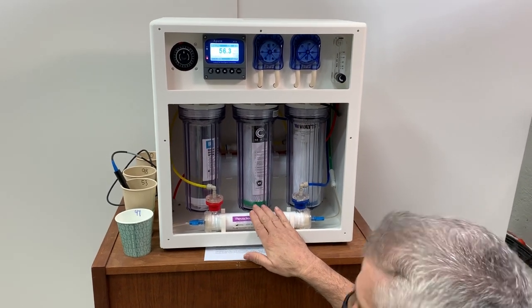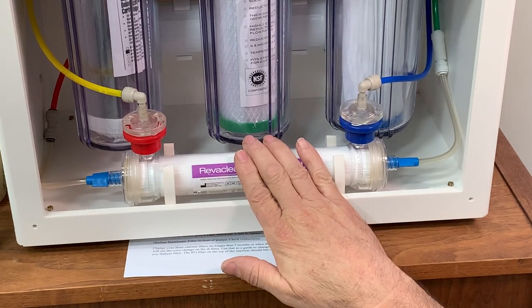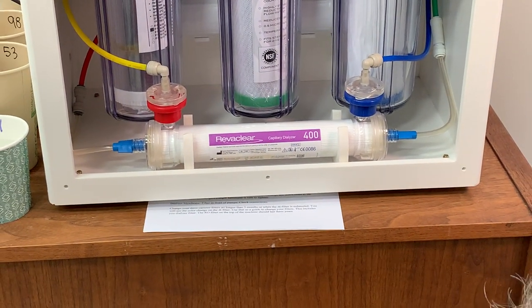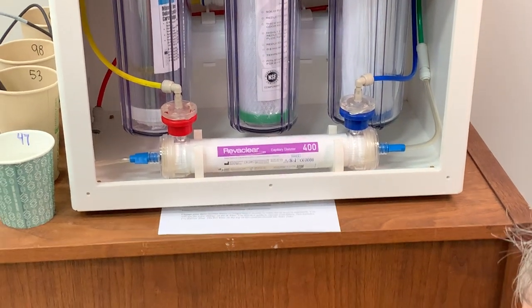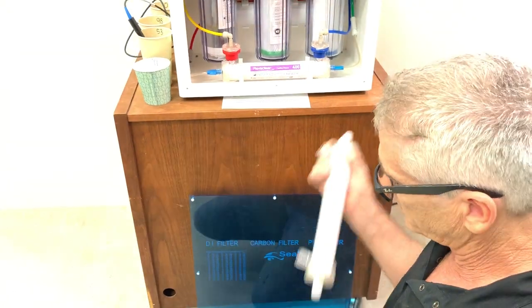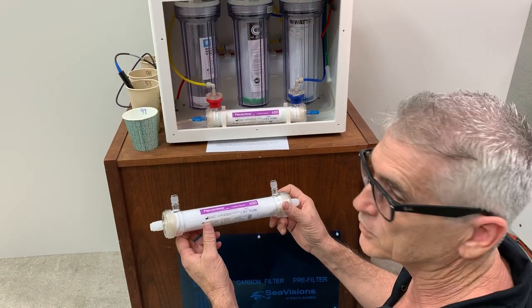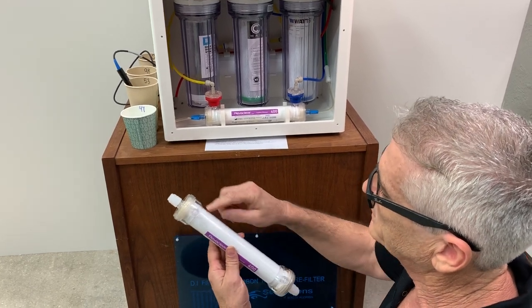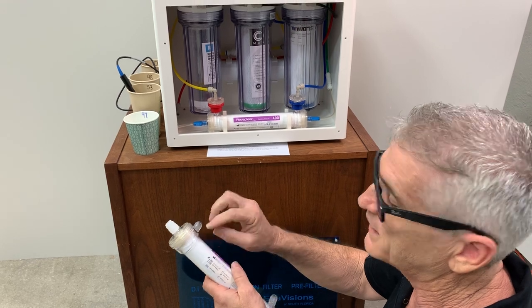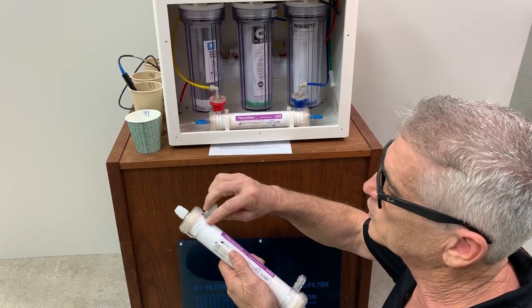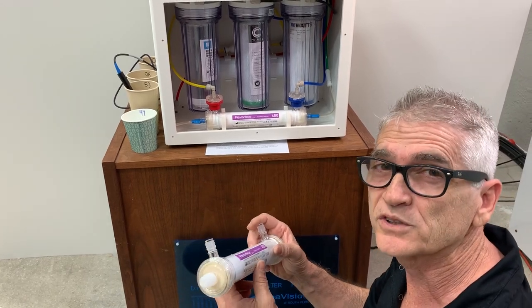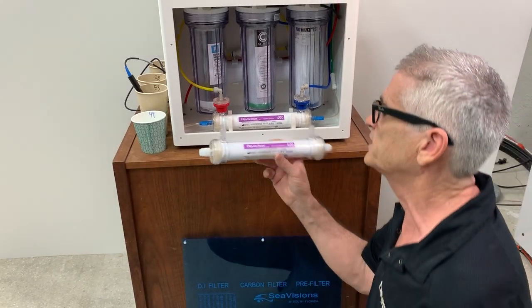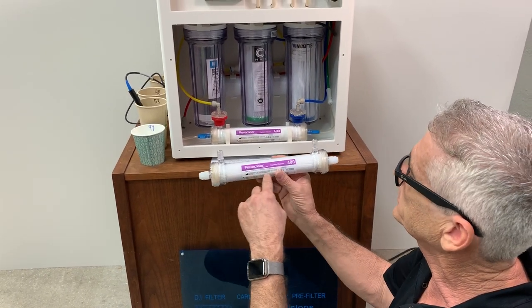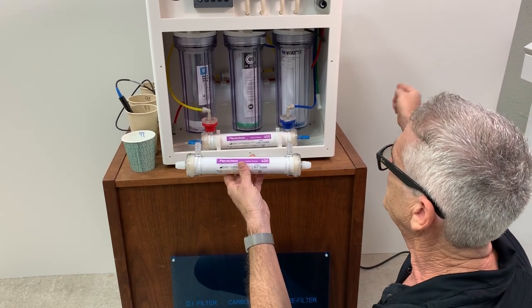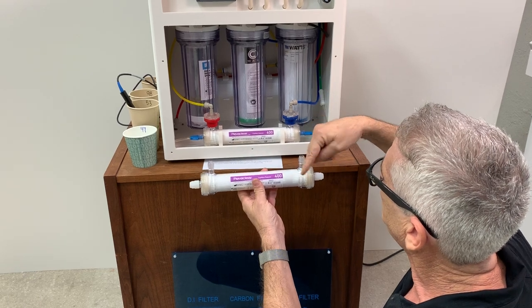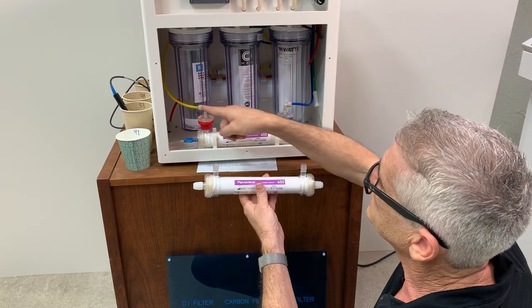Now, I hope you've read about how this device works. In short, this is a human artificial kidney that is in actual use on humans. And what happens in this type of filter, they're called ultra pure filters, is there are like 10,000 strands of filament in here, and those strands are hollow. The outer core of the filament has pores, and they measure those pores in Dalton, so it's very fine. This is typically used for human blood to be run through the center of this core, and it'll come out this end. At the same time, deionized water will come in the top, circulate around those pores, and exit out here as waste.